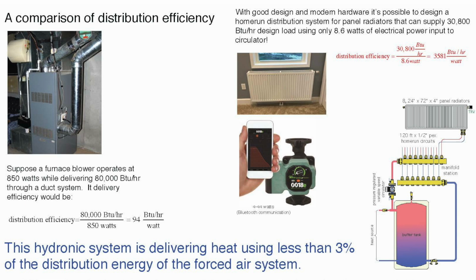Now, here's a hydronic system concept. It's a buffer tank. Doesn't matter what heats the buffer tank. It's a manifold. It's got 8 circuits that are half-inch tube, 120 feet total, 60 feet out, 60 feet back. So 120-foot circuits going to panel radiators. And those are pretty big radiators. Those are 24 by 72-inch radiators. That system was designed around 110-degree water at design, okay?